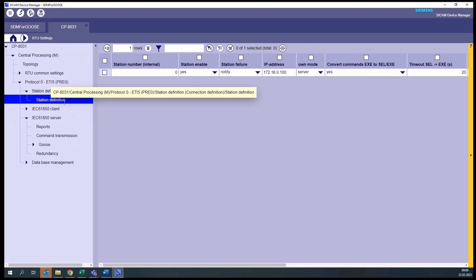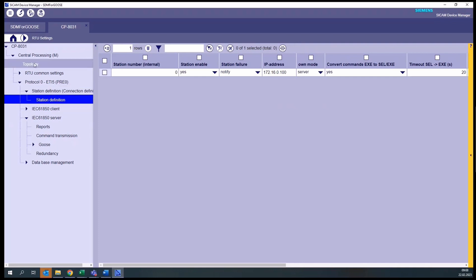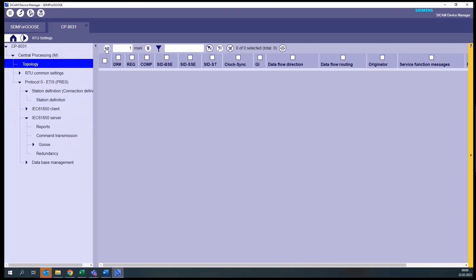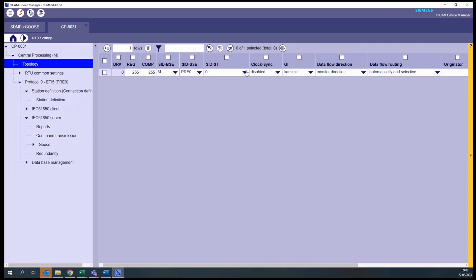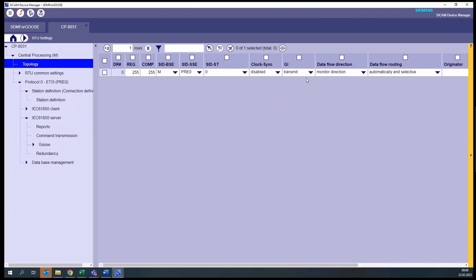Now, in the next step, remember that for every station you define on one protocol element, you need to create one entry in the topology. So you add one line there, select the protocol element and the station. For this station, the SICAM A8000 is sending information, so the data flow routing must be set to monitor direction. This is the first part that we must do in our configuration.